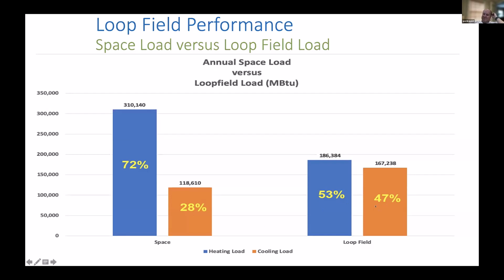And why is that? Because in the wintertime, we get a certain amount of heat energy from the compressor power, which ends up as heat in the space. In the summertime, that compressor energy also needs to be rejected. So that compressor energy needs to be added to what the loop field is seeing here.